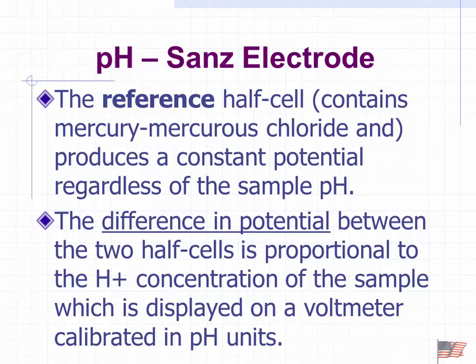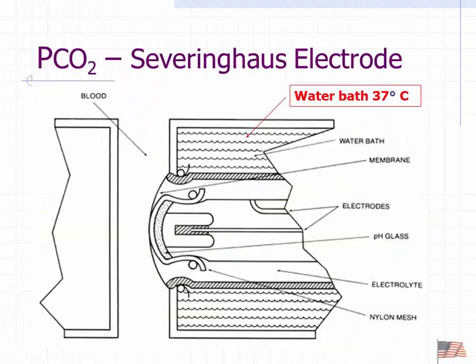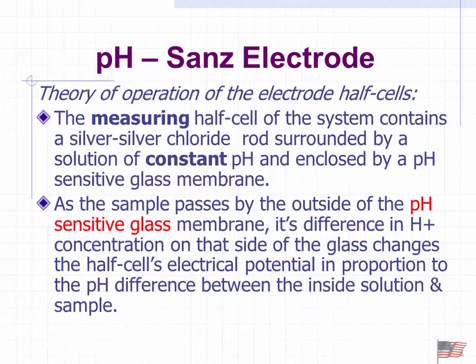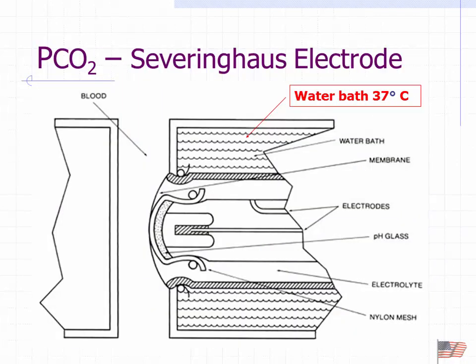So the reference cell, again, has this mercury chloride. And it produces a constant potential regardless of the pH. The other one is actually looking at what the pH is, and that difference in potential is proportional to how much hydrogen ions are present, and we can measure that difference as a voltage. Did you say one's a reference, and then what was the other one? Measurement. One's doing the measurement, one's just there to compare it to. So it's looking at the difference between the 2.